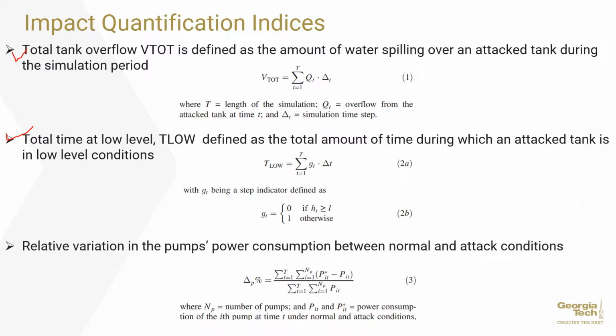The second one is the total time at low level, or T-low, which is defined as the total amount of time during which an attacked tank is at low level. Again, the greater this value, the more significant the attack. And the third one is the relative variation in pump power consumption. It's basically a percentage, the ratio to normal condition. The higher this value, the more the pump has worked, which shows there is something wrong with the system, that the pump has been overused during a specific time frame.